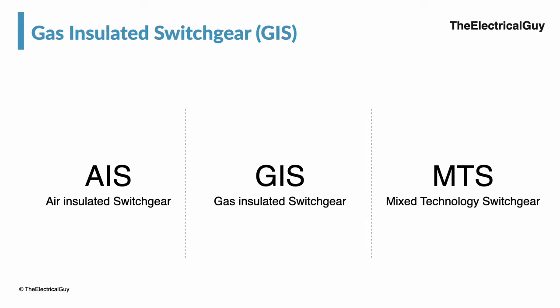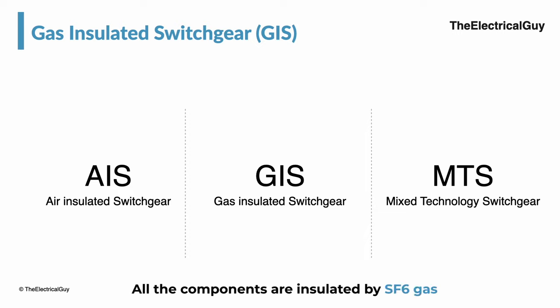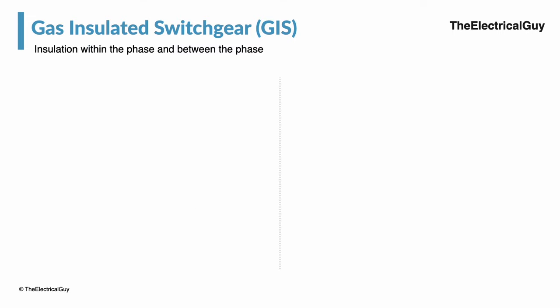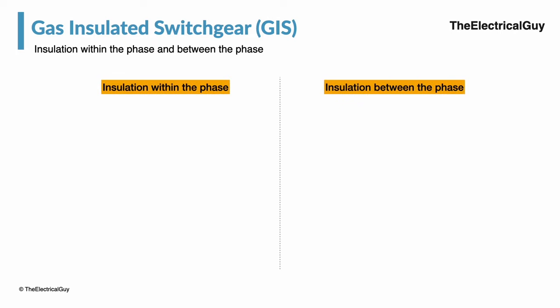As the name suggests, in GIS technology all the components are insulated by SF6 gas or any other gas. Insulation within the phase is provided by SF6 gas, and insulation between the phases is also provided by SF6 gas. We need to understand two important things: insulation within the phase and insulation between the phases.